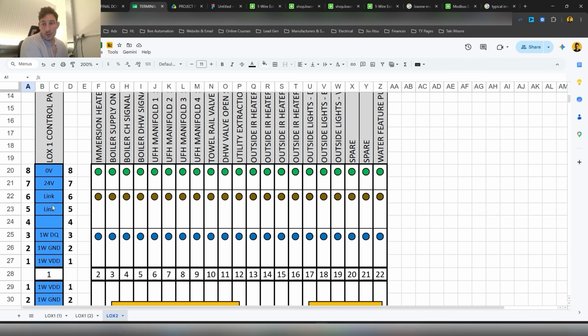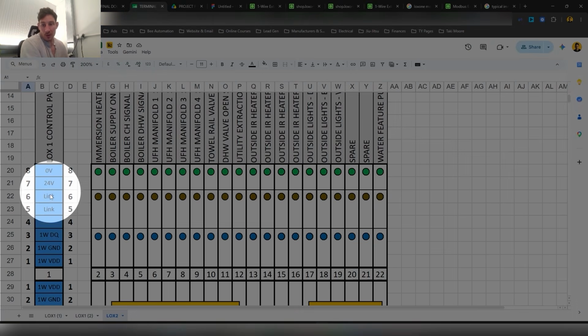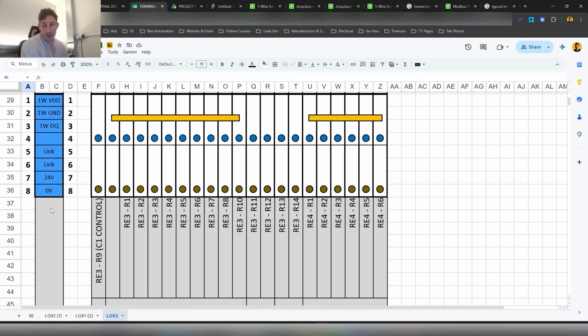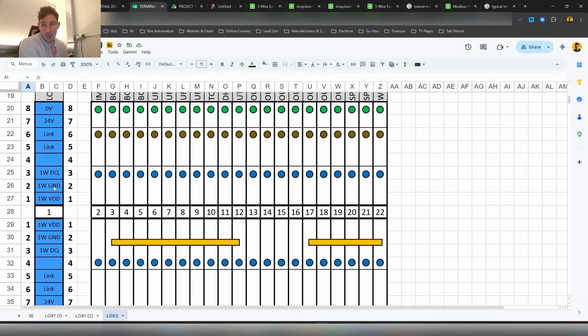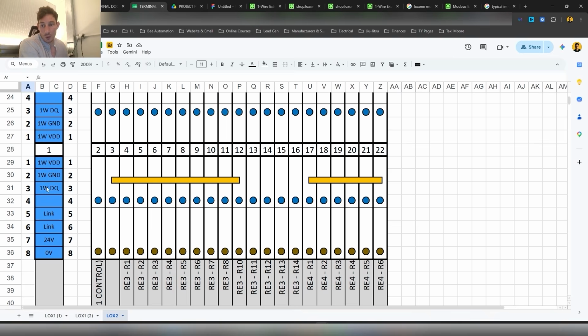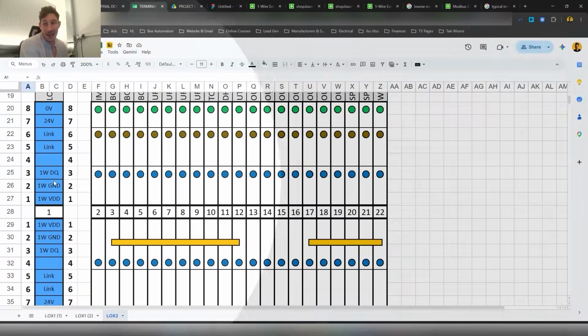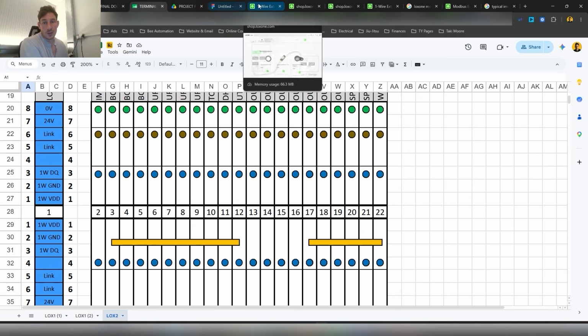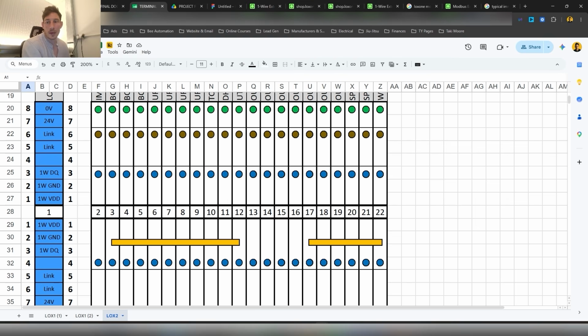So we've already talked about the 0 volts and the 24 volts and the link coming in and then being distributed in the LOX 2 panel. But you can see here, this is the one-wire D, these are the different cores: DQ, ground, and VDD. One wire DQ, one wire ground, one wire VDD. We're connecting in here, and then the outbound cable to the temperature sensors, which is what we're using one-wire for, will then be distributed along the one-wire cable infrastructure out from here.